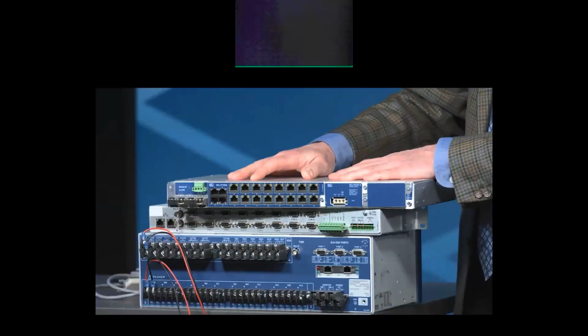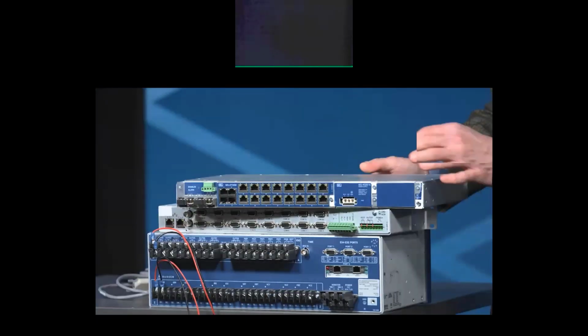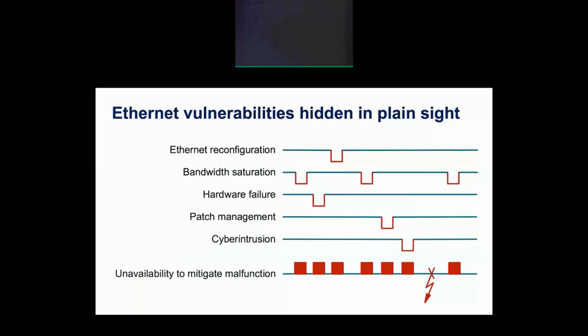Now, industrial and IT switches record their MTBF in hours, not years, and a very popular supplier publishes an MTBF of 29 years for their Ethernet switch, which is 15 times less reliable, even though that data is collected on switches in dust-free and air-conditioned environments. So you can see the disparity in products available that should be chosen and designed into a digital trip circuit.